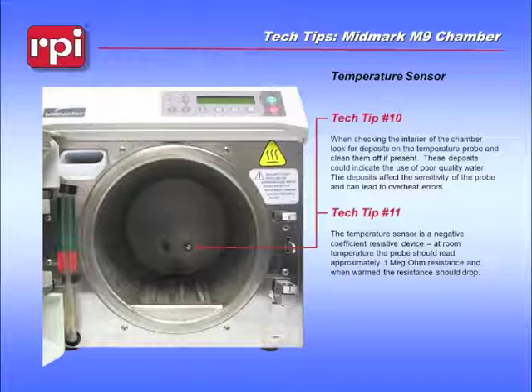It is a resistive device, and you can check its function using an ohm meter disconnected from the circuit board. Plug your ohm meter into the 2 connections on the cable at the circuit board, and you can literally touch this device and watch its resistance change as the heat in your hand heats it up.